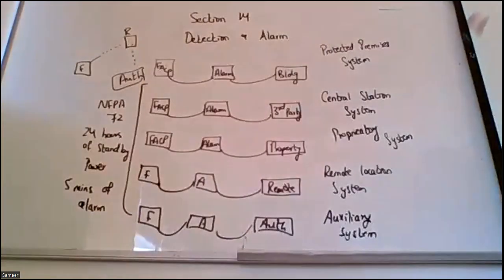They all should have 24 hours of standby power supply, and minimum 5 minutes of alarm should be there.